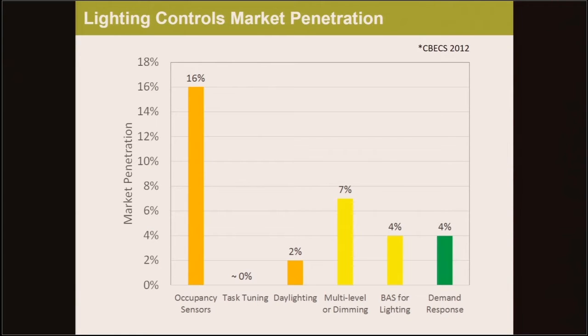Before talking about a more reliable way of demand response, let's review some market penetration of the technologies just discussed. In orange, we see occupancy sensors, which have by far the most market penetration at 16%. Task tuning doesn't happen that much but is gaining some ground. Daylighting is at 2% — so not much market penetration of the three control technologies. In yellow, we see the technologies needed to enable demand response: continuous dimming at 7%, and unlike HVAC, lighting rarely has a central control system, although this is becoming more common. In green, we see active demand response at 4% market penetration — still pretty low.